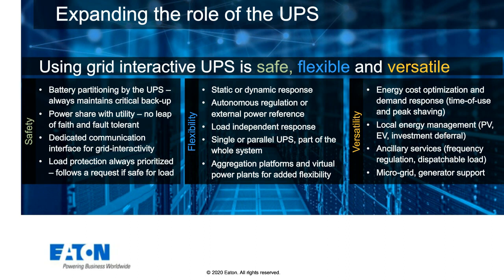But if they want the most financial compensation, they can receive an electronic signal directly from the grid operator that says we need to use some of your battery capacity, and they enable it instantaneously and disable it when necessary, again without impacting the minimum battery needed to support that data center. That gives the utility company the most flexibility.